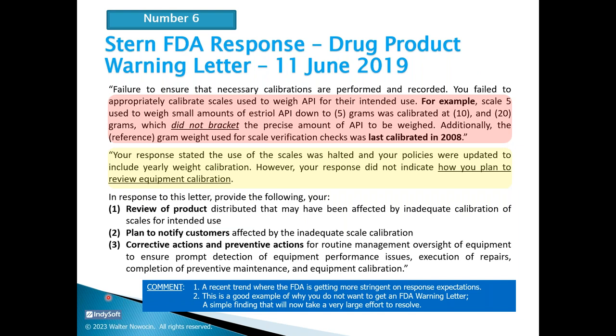Number six, stern FDA response. This has a couple things going on. One highlighted in pink here is they had a scale that was being used to weigh small amounts of their pharmaceutical drug, and it was calibrated. They were supposed to measure 5 grams, but it was calibrated 10-20, which did not bracket the precise amount of drug to be weighed. So that was one issue, and bracketing of test points of use condition is another area that FDA is taking particular note of.